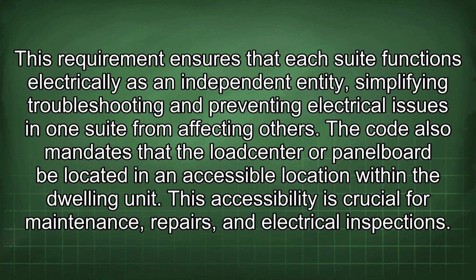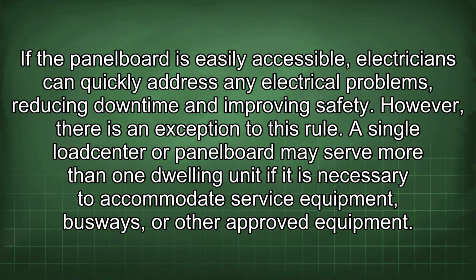This requirement ensures that each suite functions electrically as an independent entity, simplifying troubleshooting and preventing electrical issues in one suite from affecting others. The code also mandates that the load center or panel board be located in an accessible location within the dwelling unit. This accessibility is crucial for maintenance, repairs, and electrical inspections. If the panel board is easily accessible, electricians can quickly address any electrical problems, reducing downtime and improving safety.